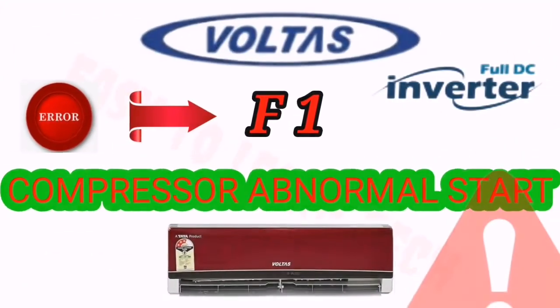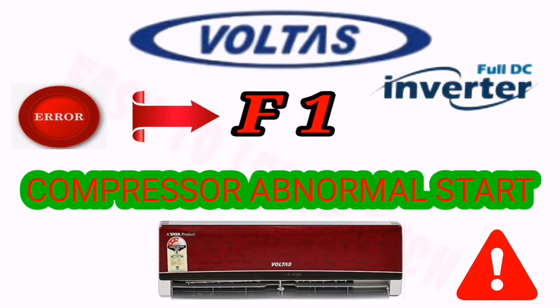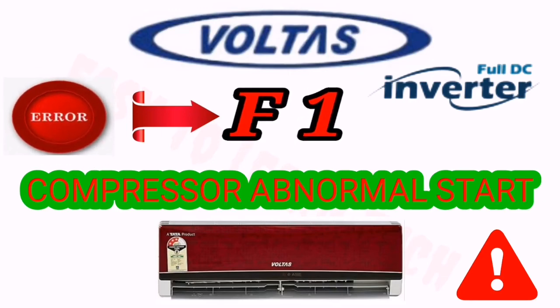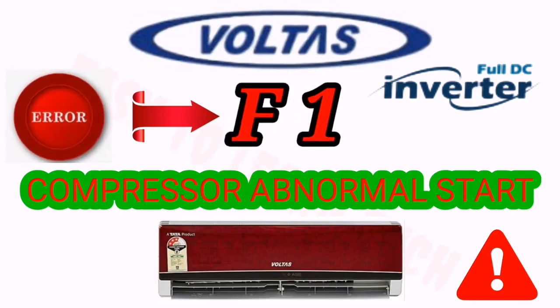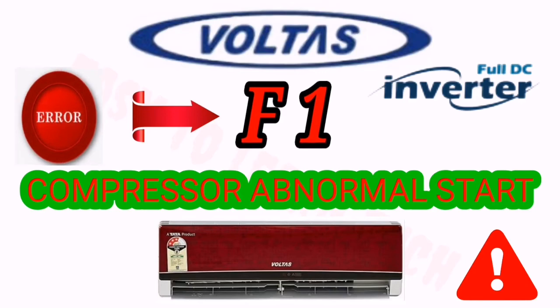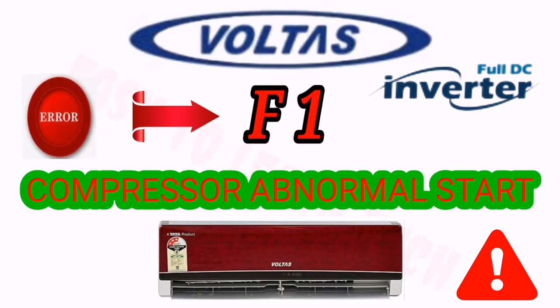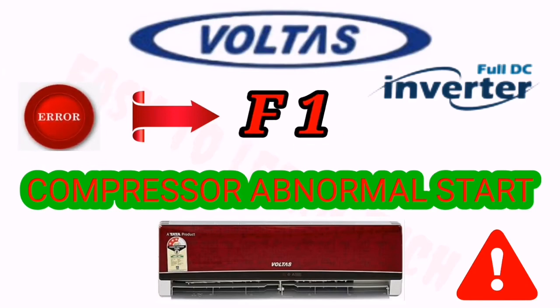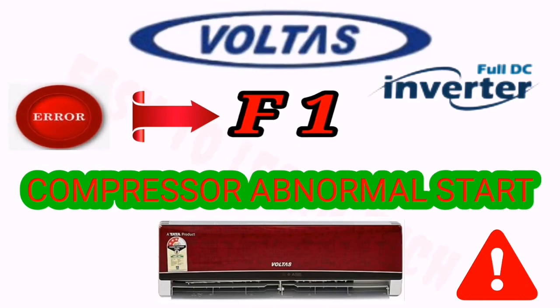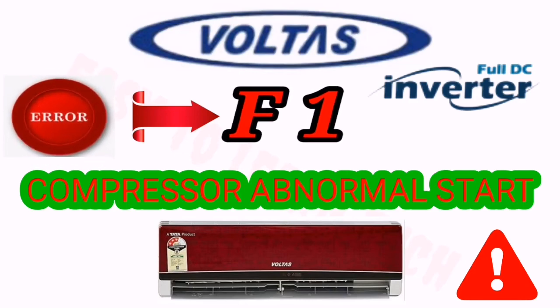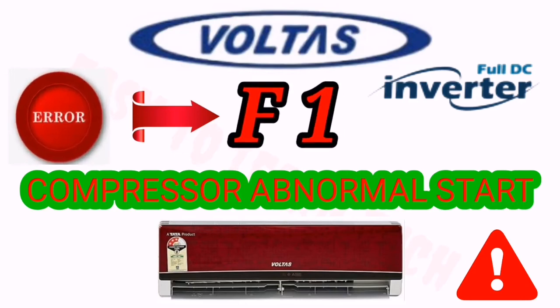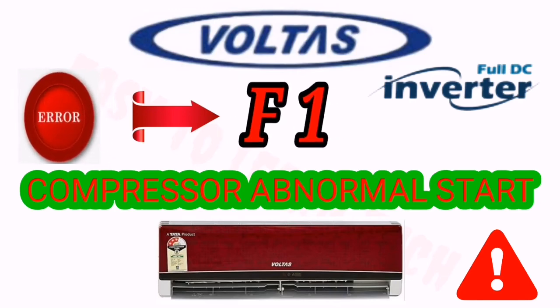Let's see the next error code. When you see F1 in your display, it means compressor abnormal start. Sometimes when our compressor doesn't start properly, it shows this error. First of all, you have to check the compressor ground, whether it is grounded or not. Then you have to check the resistance of the three terminals, whether it is okay or not. If the terminal resistance is okay and the compressor is not grounded, it means our compressor is okay.